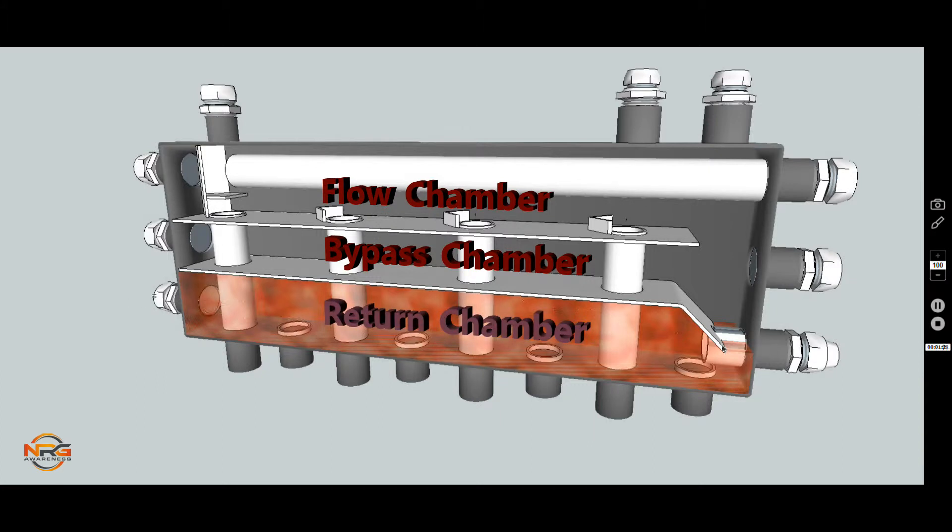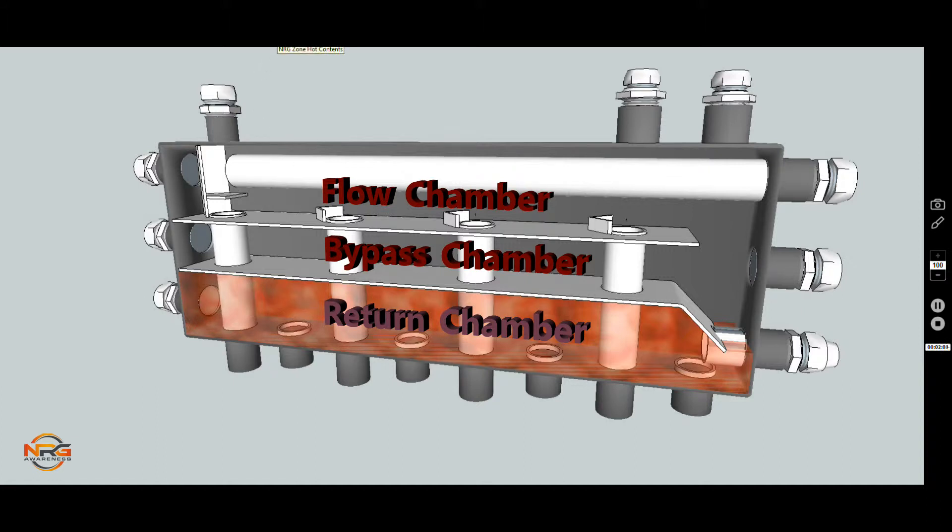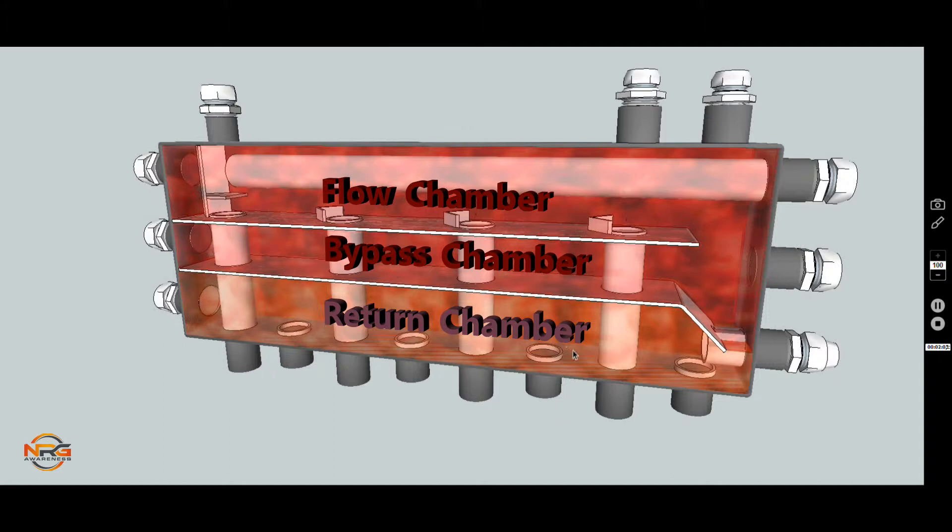Even though we have high temperature water coming in from the stove with the return going back in the bypass return, we might have the coldest water going back to our heat pump or condensing boiler. If we look at both together, you can see there's a natural stratification situation. Hottest water will collect on top as it moves through, and the colder water coming back from the zones would be available on the bottom to be drawn away by the low temperature required boiler, like condensing boilers or heat pumps.